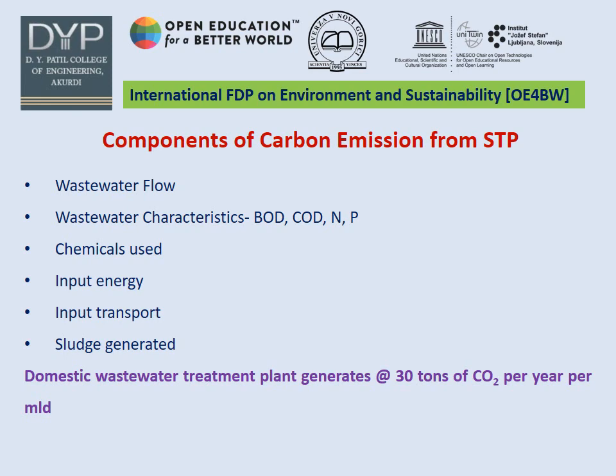Transport of treated wastewater as well as sludge from the treatment plant — including screenings, grit, compost, and ashes — all require disposal and transportation, which contributes to carbon emission. Overall, sludge generated from aerobic or anaerobic treatment leads to carbon emission. A domestic wastewater treatment plant typically generates about 30 tonnes of carbon dioxide per year per MLD of wastewater treated.